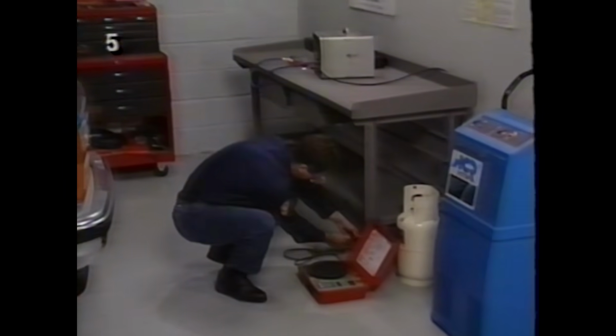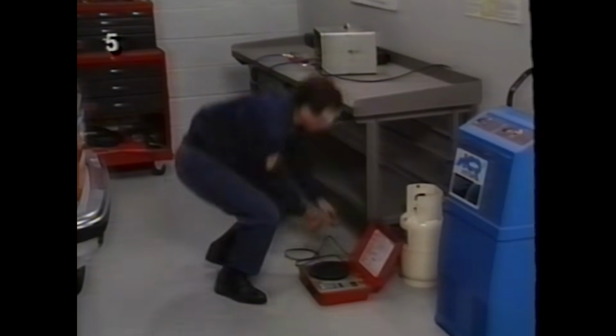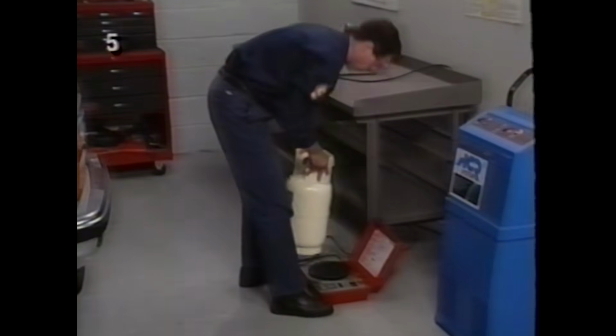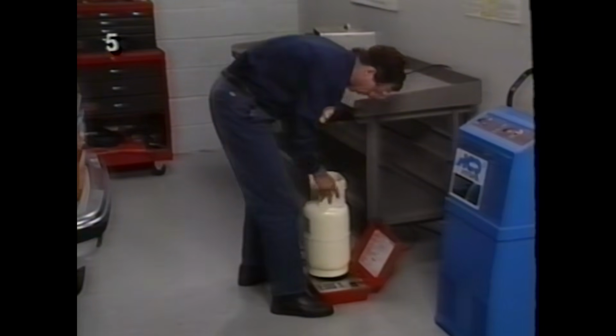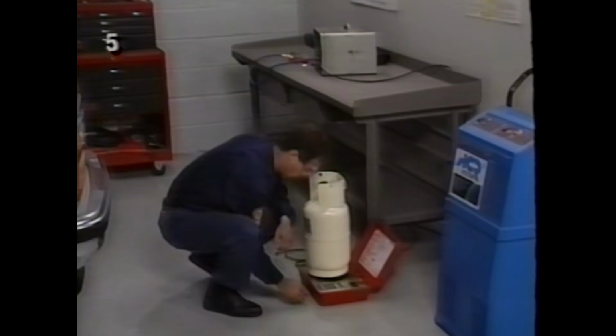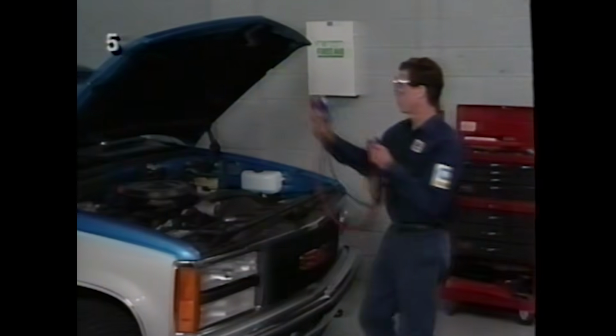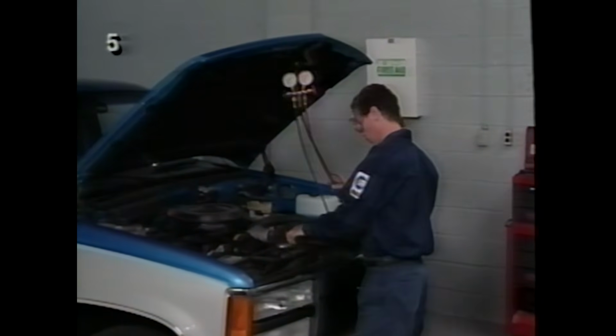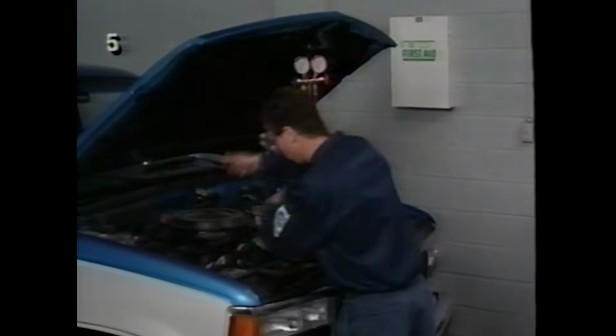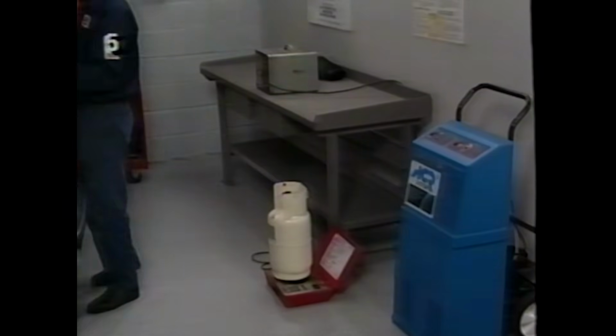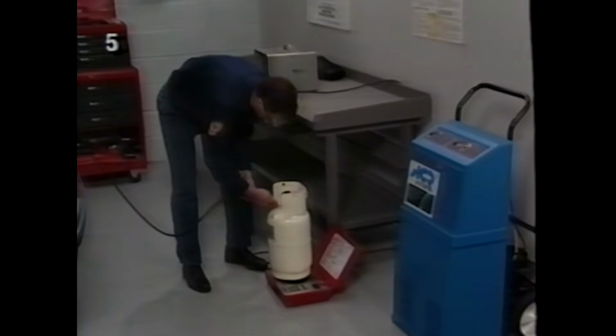You're just about ready now. Put the storage drum on an accurate scale and write down the weight of the drum. You'll be keeping an eye on the scale when the system is charging. Connect your manifold gauges this way. The low pressure gauge goes to the Schrader valve on the accumulator. Attach the center hose to the storage tank.